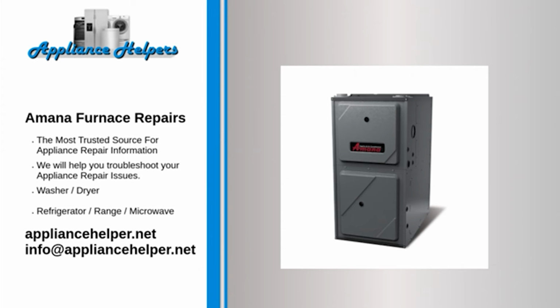Amana furnace is not heating. The igniter gets very hot and glows bright orange to light the gas burner. If the igniter fails or cracks, the furnace won't heat. To determine if the igniter is faulty, remove the igniter and inspect it for cracks. If the igniter is cracked, replace it. If the igniter is not cracked, use a multimeter to test the igniter for continuity. If the igniter does not have continuity, replace it.